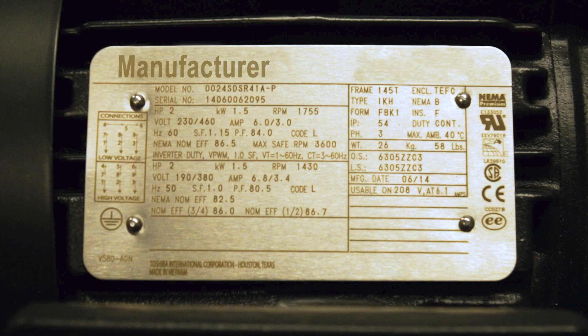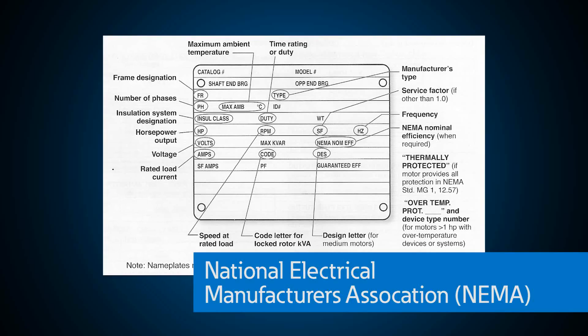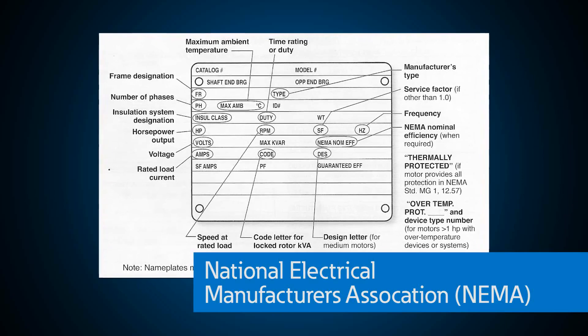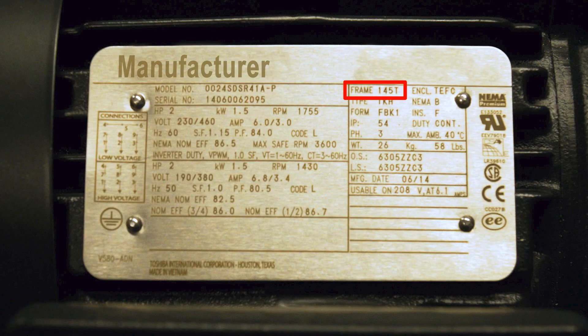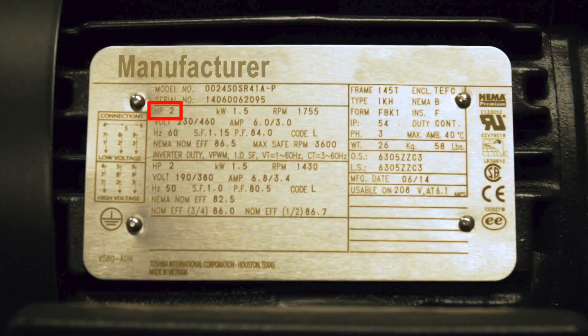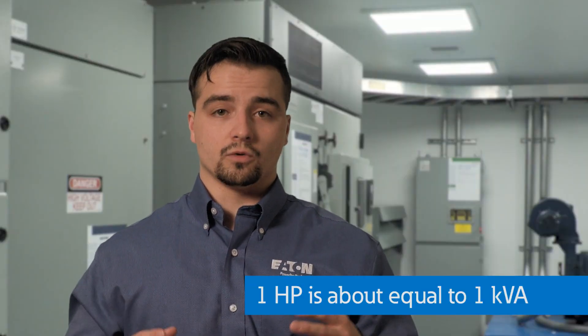Motors have a nameplate to display the necessary electrical and mechanical information for a technician or engineer. Let's take a closer look at the nameplate. This steel or aluminum plate is engraved to make the information readable for the life of the motor. Here in the US, nameplate information standards are set by NEMA, the National Electrical Manufacturers Association, but manufacturers may include other information to help with installation, operation, and maintenance of custom motors. The nameplate will list the frame designation for the mounting dimensions, the manufacturer's type which tells the function of the motor, and the power or horsepower rating. A good rule of thumb is that one horsepower is about equal to one kVA.